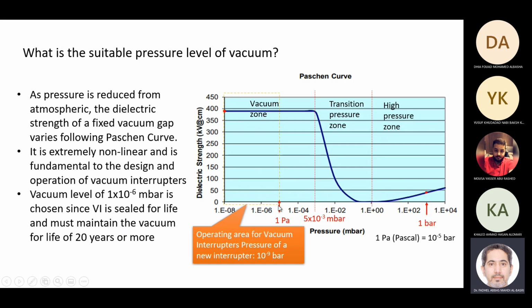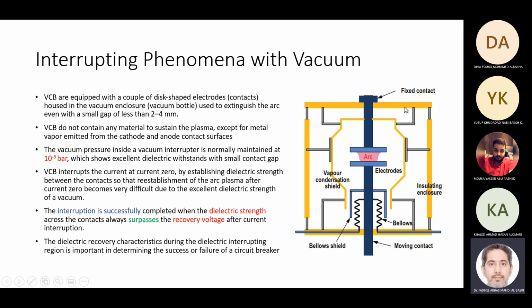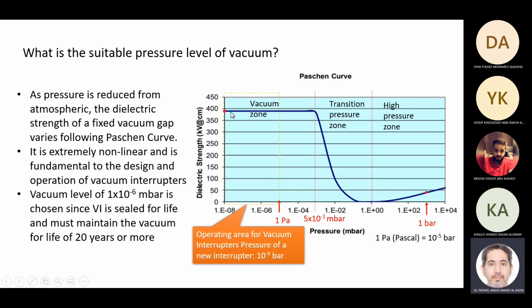Why is the vacuum at very low pressure? Because their dielectric property becomes constant at very low vacuum, at a pressure of 10 to the power minus 9 bars. And it is kept at that low level so that even when it's leaking, because vacuum tubes are like this one, the tube is sealed. And these are the contacts, sealed and under vacuum. So it's sealed for lifetime. So what they do, they try to make the vacuum low enough so that even when the vacuum reduces because of operation, it doesn't lose its property.